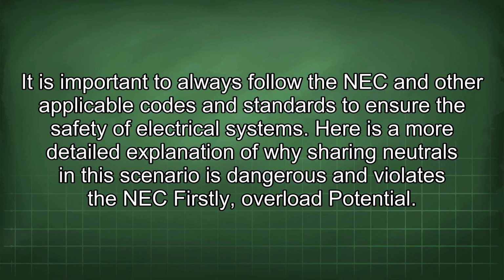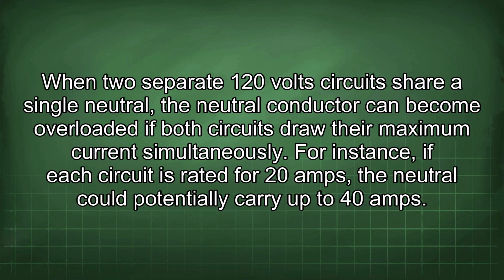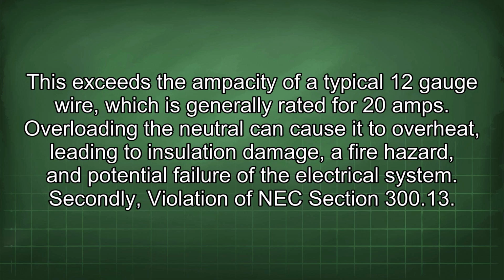Here is a more detailed explanation of why sharing neutrals in this scenario is dangerous and violates the NEC. Firstly, overload potential. When two separate 120 volt circuits share a single neutral, the neutral conductor can become overloaded if both circuits draw their maximum current simultaneously. For instance, if each circuit is rated for 20 amps, the neutral could potentially carry up to 40 amps. This exceeds the ampacity of a typical 12-gauge wire, which is generally rated for 20 amps. Overloading the neutral can cause it to overheat, leading to insulation damage, a fire hazard, and potential failure of the electrical system.